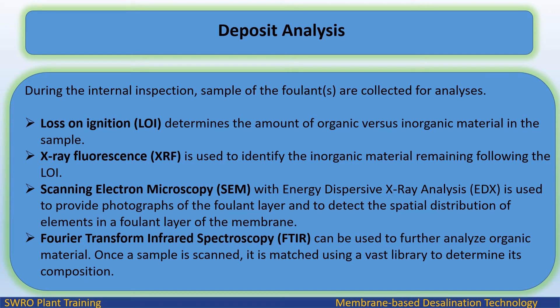Deposit analysis: During the internal inspection, samples of the foulants are collected for analysis. Loss on ignition (LOI) determines the amount of organic versus inorganic material in the sample. X-ray fluorescence (XRF) is used to identify the inorganic material remaining following the LOI. Scanning electron microscopy (SEM) with energy dispersive X-ray analysis (EDX) provides photographs of the foulant layer and detects the spatial distribution of elements. Fourier transform infrared spectroscopy (FTIR) can further analyze organic material — once a sample is scanned, it is matched using a vast library to determine its composition.